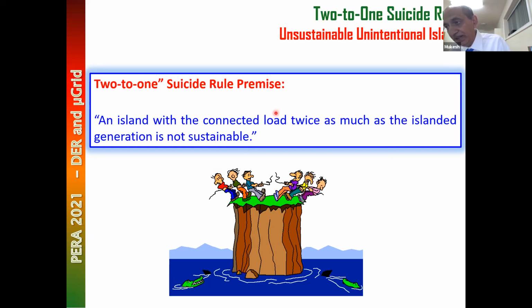What that means is, if you form a microgrid where the load is twice as much as the generation, that microgrid is not going to be sustainable. The protection and control of the generator are going to kill it. So if there's a fault, you separate from the utility, and you separate so that the generation in the island is half the load in the island. The fault is going to self-clear because the source is going to go on a path of suicide. The load will kill it.